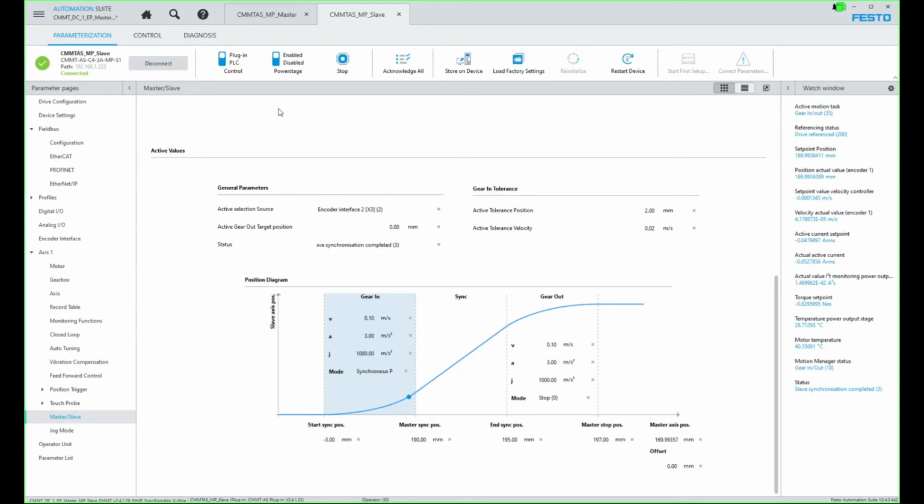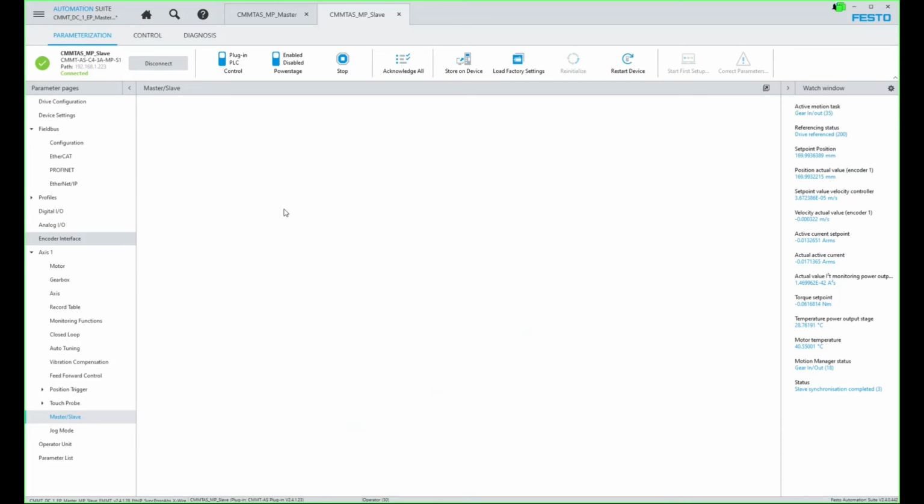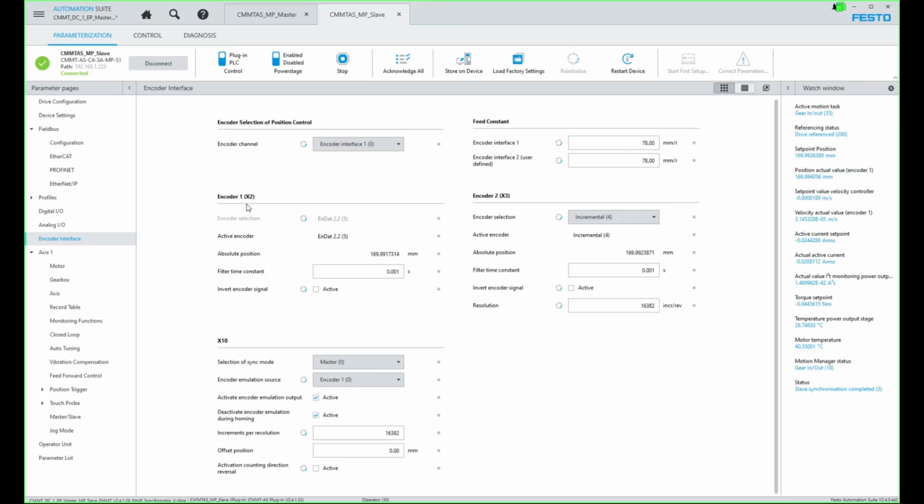Other troubleshooting we can do in here is not much. So what we need to set up in the PLC is the master position, so that when we have a power off, power on, anything along that line, we align the encoder that's on the motors, which is the X2 port right here. Then we need to align this position here with what the position is right here.